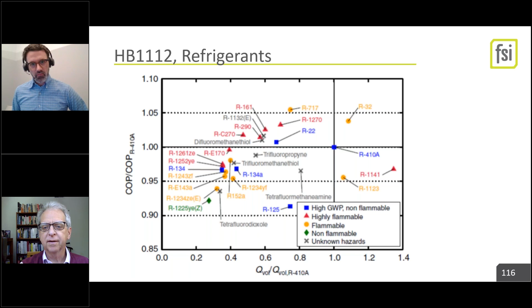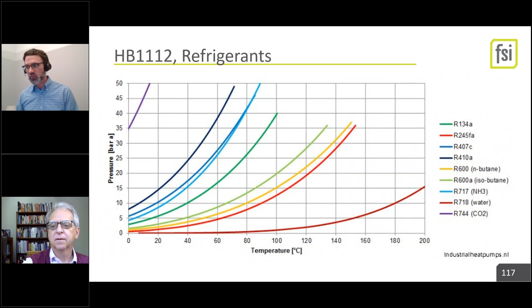Right, and it's going to start coming with things like this equipment must be installed in a room bigger than X. You know, it's that sort of level of detail. Here's your refrigerants, and way off to the left is the pressure. That R744 is CO2, so that's the big hindrance to CO2. I think it's going to be a long time before we see CO2-based field joint systems. It may never happen because it's such high pressure. But all the other ones, we can get there.